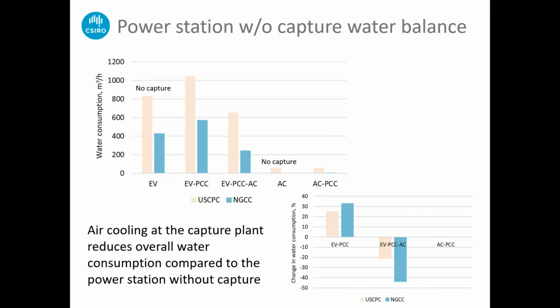It's around 25% for the coal-fired power station, and percentage-wise, it's more than 30% for the gas-fired combined cycle, which is significant. But if we, instead of using that evaporative cooling for the capture plant, use air cooling, we can actually reduce that additional water requirement to negative values. So we actually have a lower water consumption for the option where the power plant is evaporative cooled and the capture plant is air cooled. And that's quite an important finding, because there's no need to assume that if you add PCC to a power plant, you immediately end up with a higher water consumption if that capture plant is then air cooled.